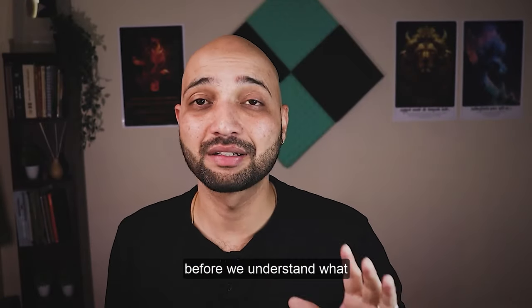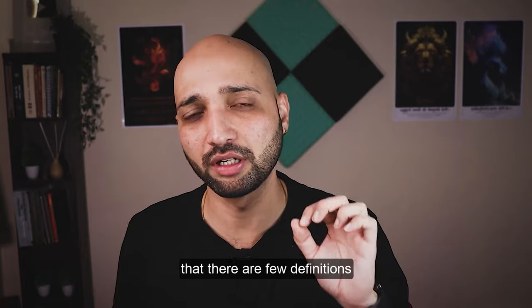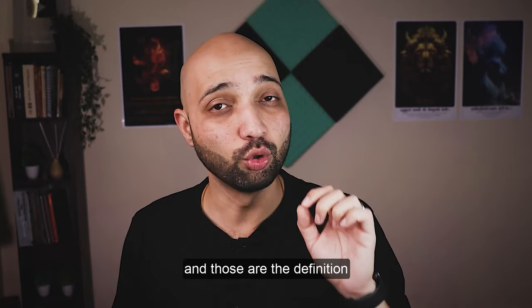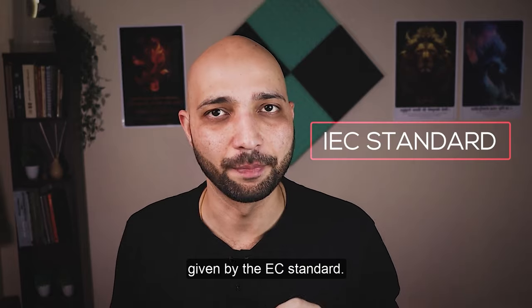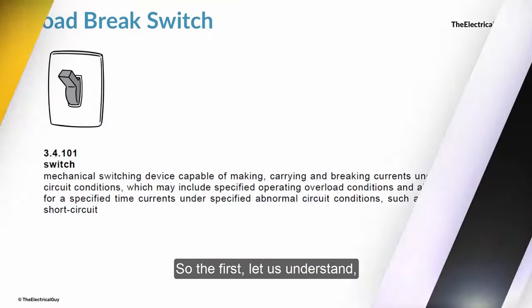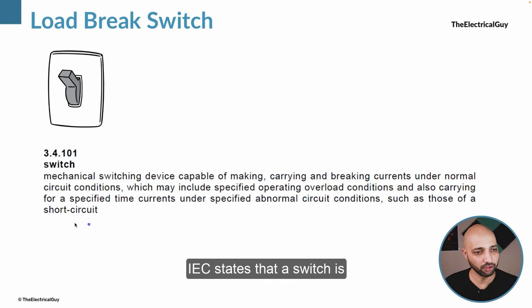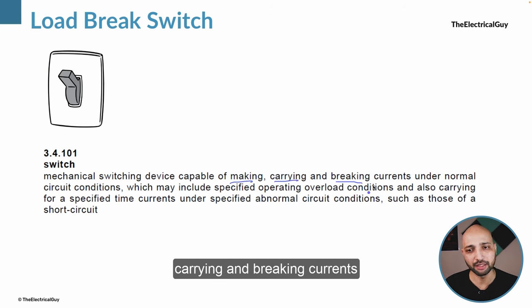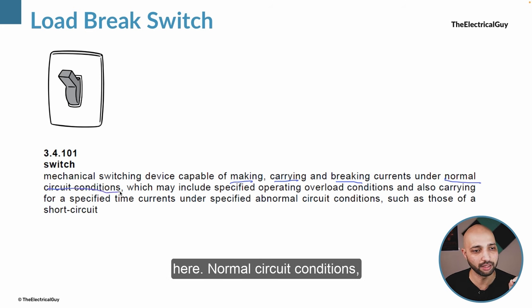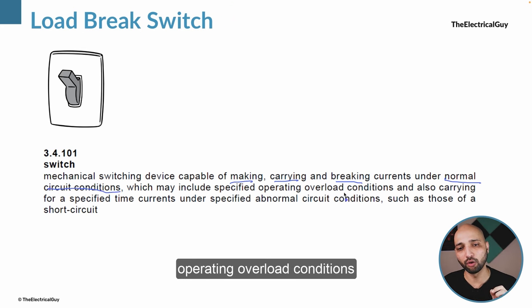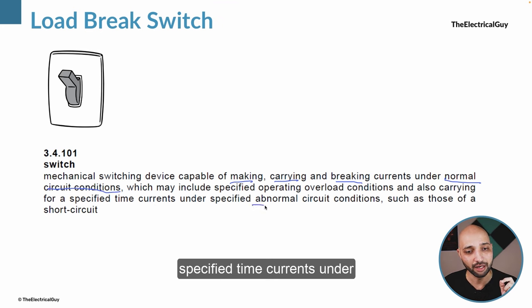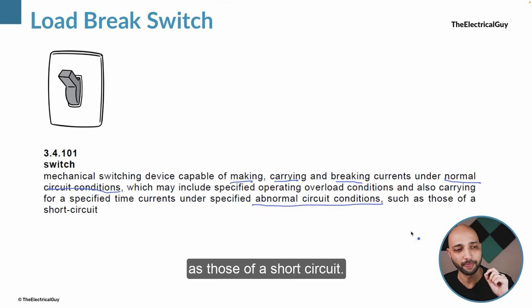Before we understand what a load break switch is, there are a few definitions we should understand — those given by the IEC standard. The first one is: what do we mean by a switch? IEC states that a switch is a mechanical switching device capable of making, carrying, and breaking currents under normal conditions, which may include specified operating overload conditions, and also carrying for a specified time currents under abnormal circuit conditions such as those of a short circuit.